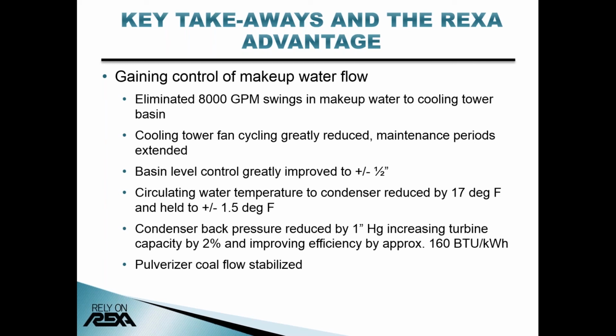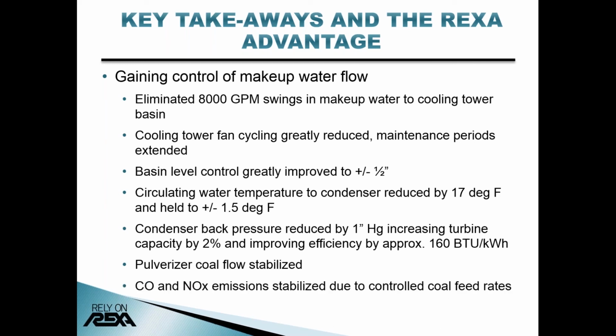All right, and then we certainly can't forget what that does to emissions. We were always running pretty well in hand on emissions, but we were overachieving in order to make sure that we didn't have any exceedances. And with the stable coal flow and tighter controls on our boiler O2 set points, we could approach closer to our permit limits without fear of having an exceedance. And we're also saving significantly on our ammonia usage for the NOx controls.